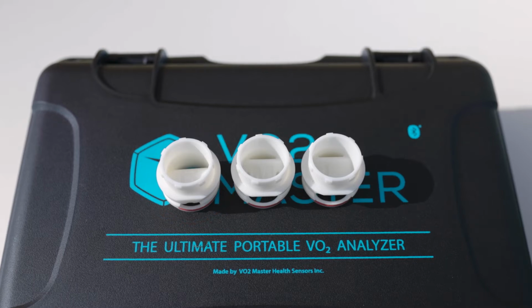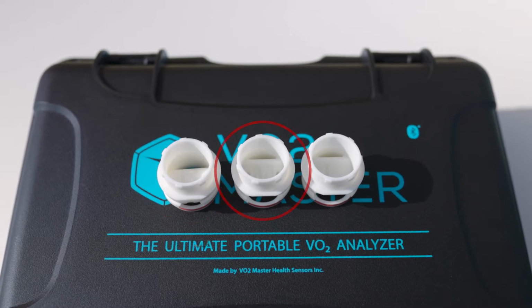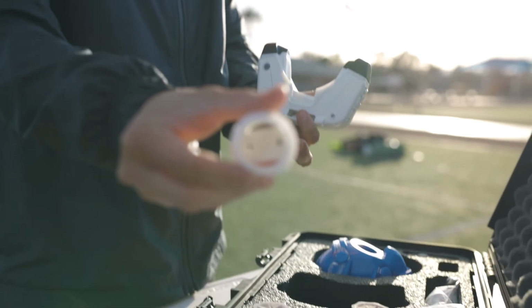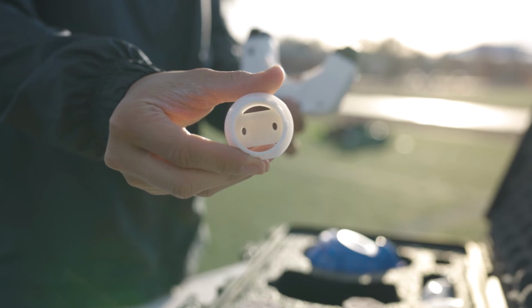The user piece indicated by the embossed letter M is used for exercise testing at a ventilation range between 30 and 160 liters per minute. Last, the user piece that is indicated by the embossed letter L is used for exercise testing at a ventilation range between 40 and 220 liters per minute. For this demo, I'll be using the M user piece.